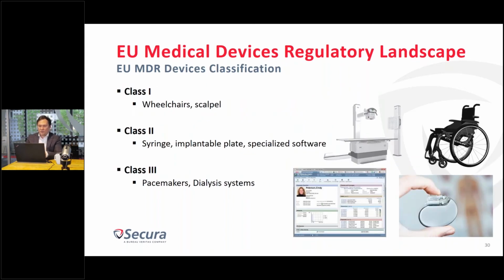We were introducing before the categories of devices under the medical device regulation in the European Union. Just to provide some examples, for class one, which applies to non-invasive devices, you can think about wheelchairs or scalpels. Class two applies to invasive devices, so you can think about things such as syringes or implantable plates or implantable elements into the body, but also specialized software would most of the time fall into class two, unless it is low-risk software, then it will fall into class one. And finally, class three deals with really high-risk medical devices, the ones that either have a direct impact on a life sustaining function or are in touch with the nervous system. As an example, you can think about pacemakers or more sophisticated dialysis systems.